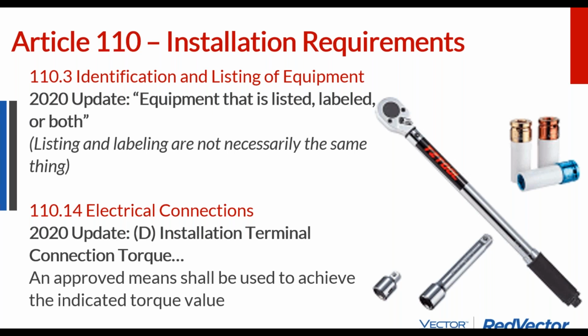And so where installers who are abiding by this do it is, they'll just have some guy with a torque wrench come through afterwards to make sure that all the connections are torqued to spec. So in the solar industry, you might mount the array, and then as you go, a guy follows it up with a torque wrench to make sure every piece was tightened to the right value. Of course, that doesn't really prevent over tightening.